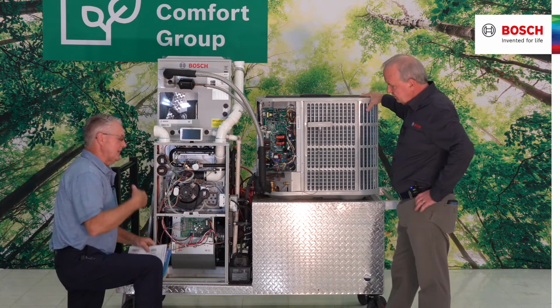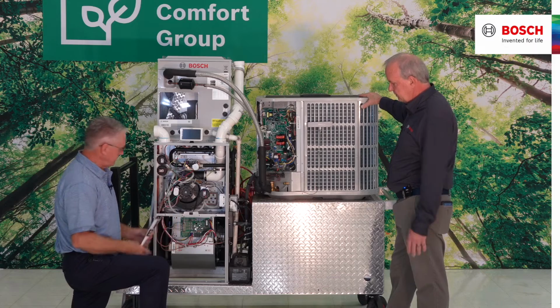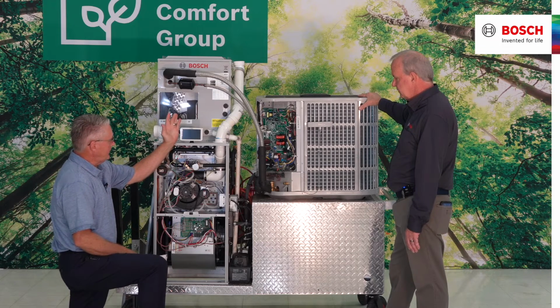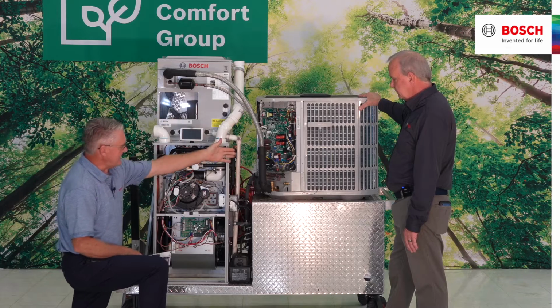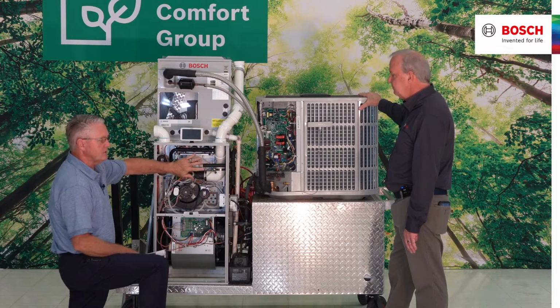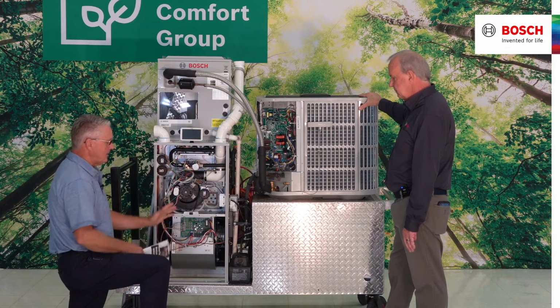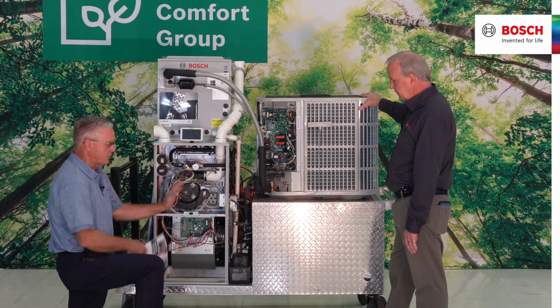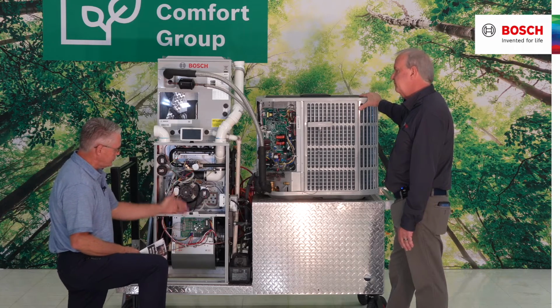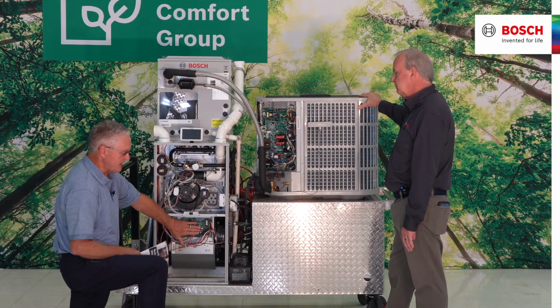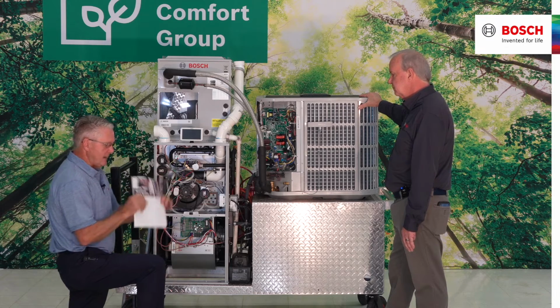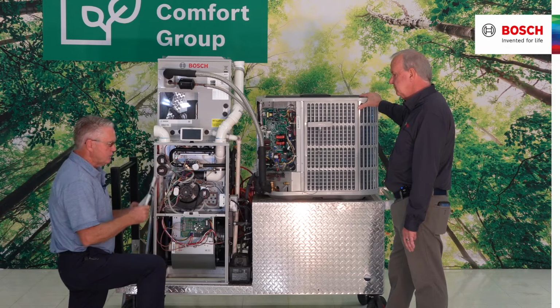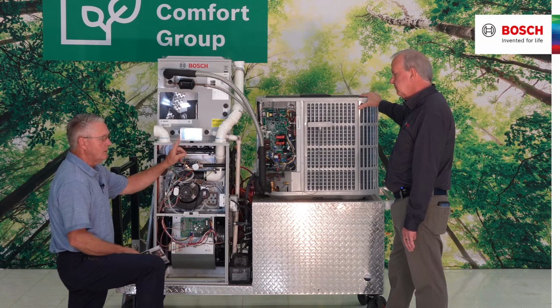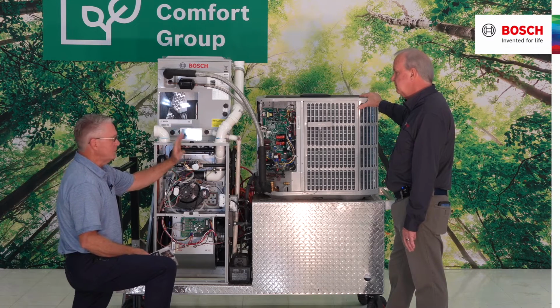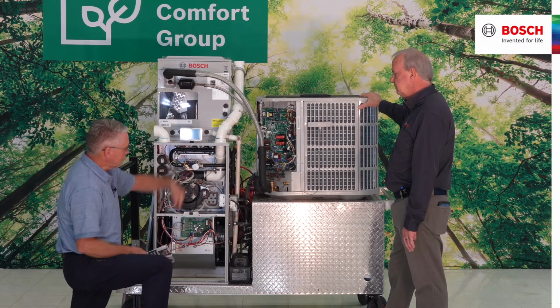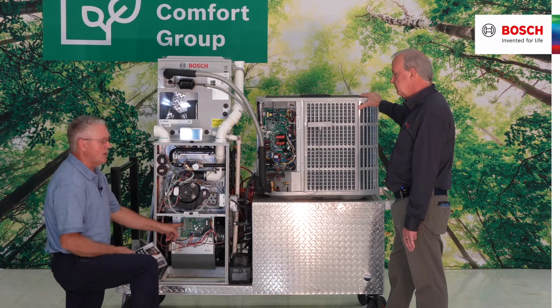Awesome. So Ken, I get a question probably two times a month about wiring up the BCC 100 to the IDS unit utilizing the gas-fired furnace. We have a red, a yellow, a green, a common, a power wire termination down here, or a terminal block, where we're going to bring those wires to the terminal on the BGH furnace. But the installation manual and our quick start guides show us where the B wire, the reversing valve energizing wire, goes from the thermostat to the condensing unit, but it does not hook up on the board.